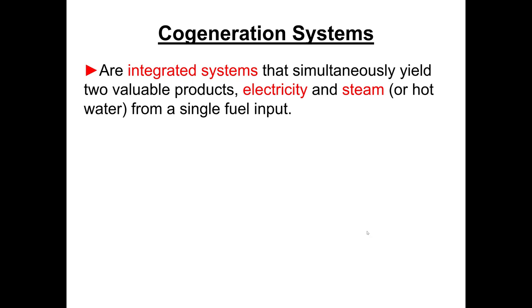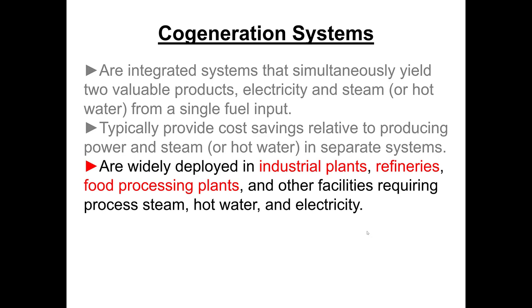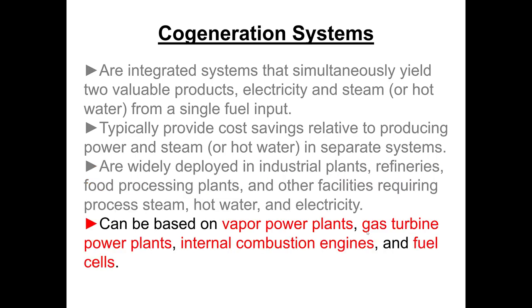Moving on to cogeneration systems: cogeneration is not a power cycle system in itself but rather a combination of a power plant with a community's need for hot water or steam, in order to provide cost savings in generating both commodities — power and heating steam. These processes are widely used in industrial plants, refineries, and food processing plants that require process steam as well as electricity. Cogeneration doesn't strictly require a Rankine cycle; it only requires any consistent, relatively high-temperature heat source.